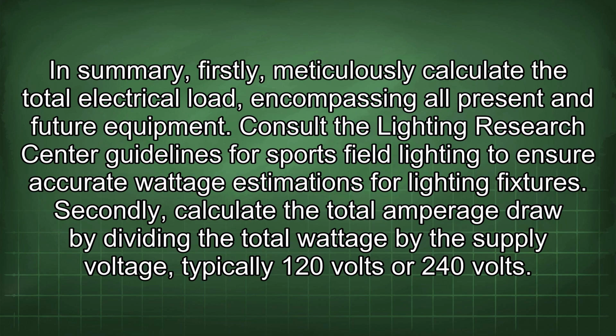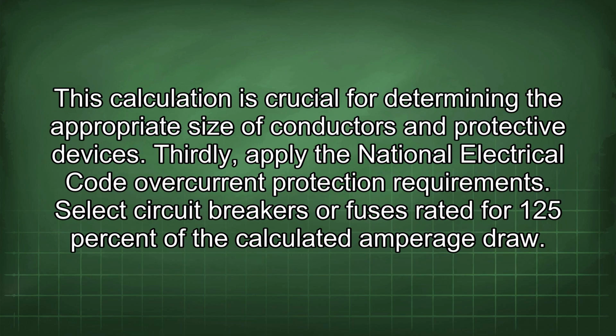In summary, firstly, meticulously calculate the total electrical load, encompassing all present and future equipment. Consult the Lighting Research Center guidelines for sports field lighting to ensure accurate wattage estimations for lighting fixtures. Secondly, calculate the total amperage draw by dividing the total wattage by the supply voltage, typically 120 volts or 240 volts. This calculation is crucial for determining the appropriate size of conductors and protective devices.